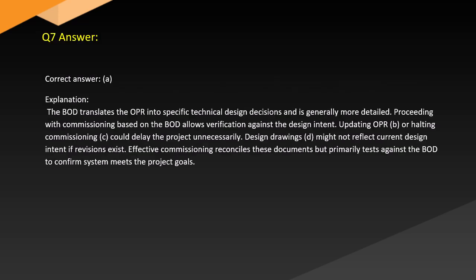Answer. Correct answer: A. Explanation. The BOD translates the OPR into specific technical design decisions and is generally more detailed. Proceeding with commissioning based on the BOD allows verification against the design intent. Updating the OPR (B) or halting commissioning (C) could delay the project unnecessarily. Design drawings (D) might not reflect current design intent if revisions exist. Effective commissioning reconciles these documents but tests against the BOD to confirm the system meets the project goals.